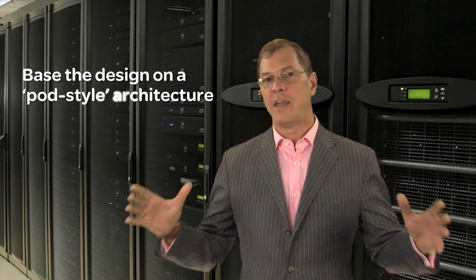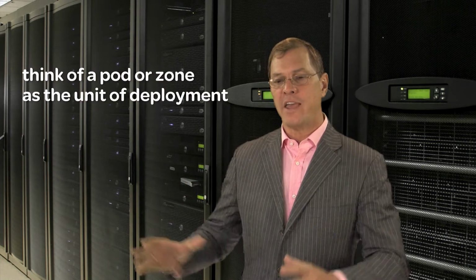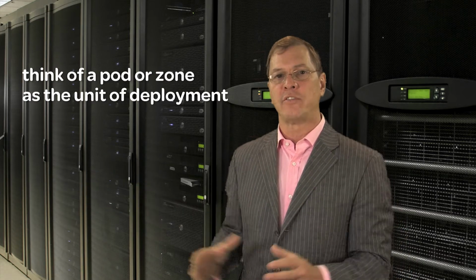Well, I think anybody who's designing a data center today is either designing specifically with a cloud environment in mind, or they should have an expectation that a growing fraction of their total installation will be of a cloud type architecture. And we see a number of key approaches that ought to be considered when designing a data center to be cloud compatible. One is, we really think it should be designed based around a pod style architecture where we don't think about the rack or cabinet as the unit of deployment, but think about a set of cabinets in a zone as the unit of deployment.